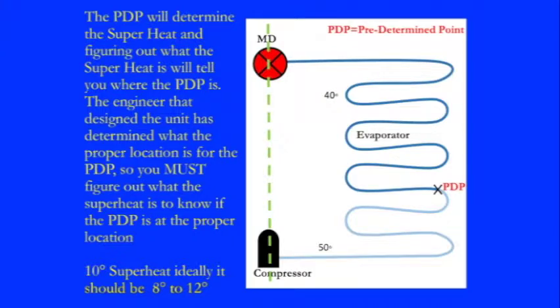In this example, we have a 40-degree coil and the temperature at the outlet is 50 degrees. When we subtract the two, we get 10 degrees of superheat. To me, that's ideal—we want somewhere between 8 to 12 degrees of superheat.